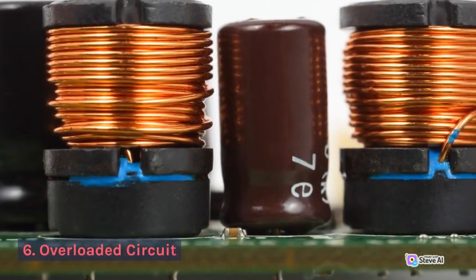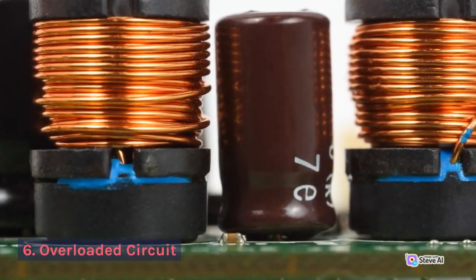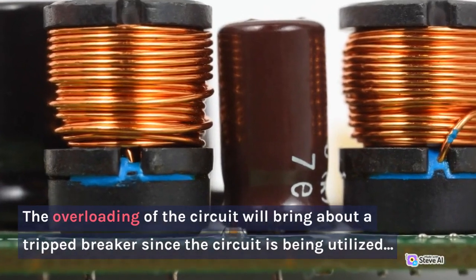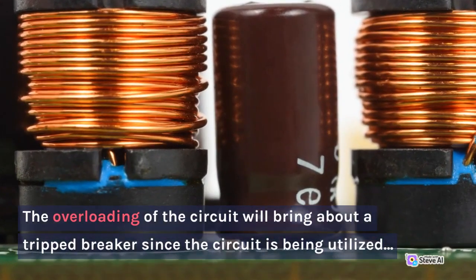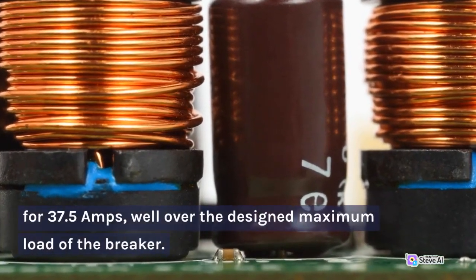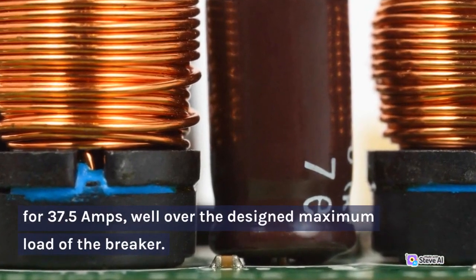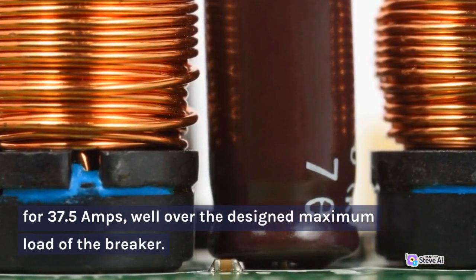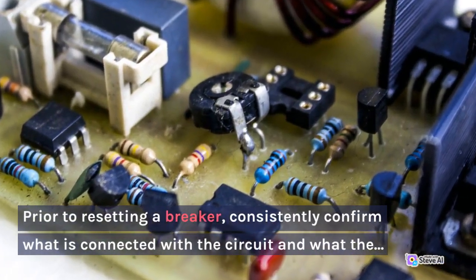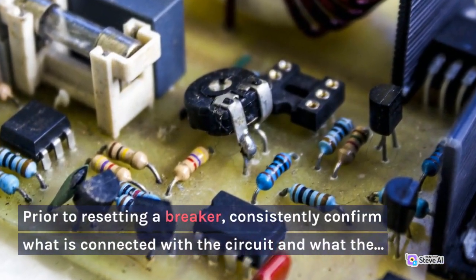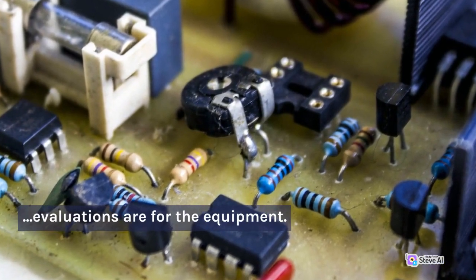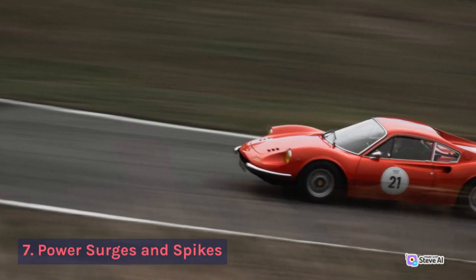6. Overloaded circuit. The overloading of the circuit will bring about a tripped breaker since the circuit is being utilized for 37.5 amps, well over the design maximum load of the breaker. Before resetting a breaker, always confirm what is connected with the circuit and what the ratings are for the equipment. 7. Power surges and spikes.